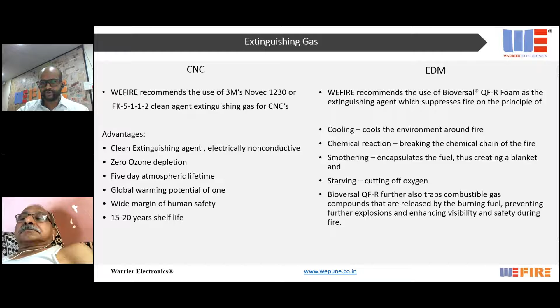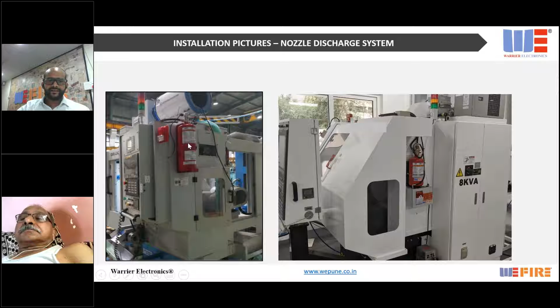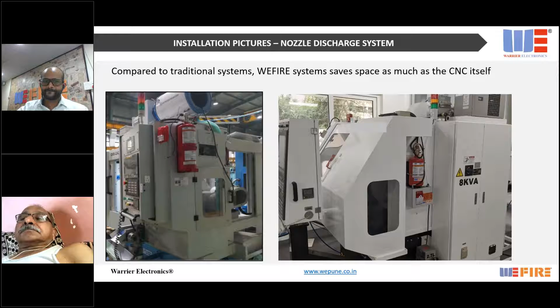Some of the installation pictures on a CNC machine. So we have a cylinder which is mounted alongside. The advantage of these systems is that they save a lot of space compared to conventional CO2-based systems. It saves as much space as the CNC machine itself, because the use concentration of Novec 1230 is just 4.2% to 6% compared to CO2, which could go up to 60% for a CNC machine application. Hence, for a location where you need to use 10 cylinders of CO2, if you replace it with Novec, you will only have to use just 4 cylinders of Novec 1230 or FK-5-1-1-2.